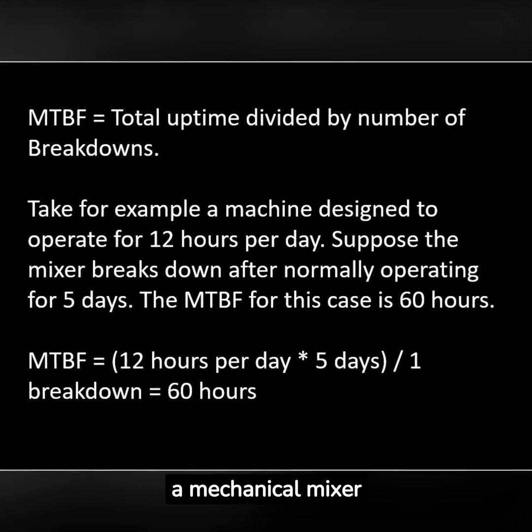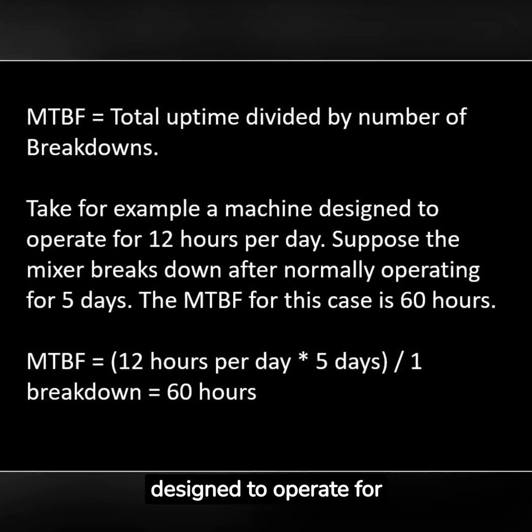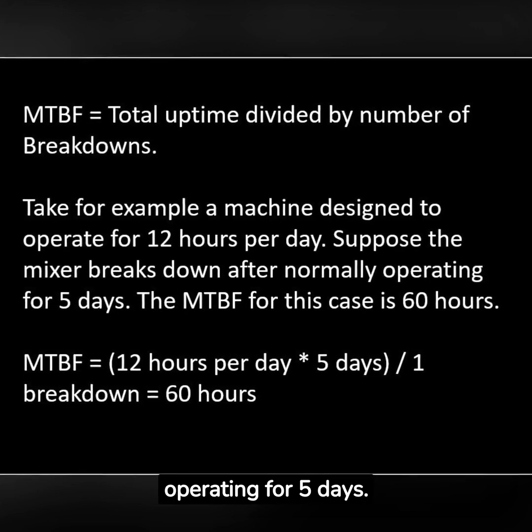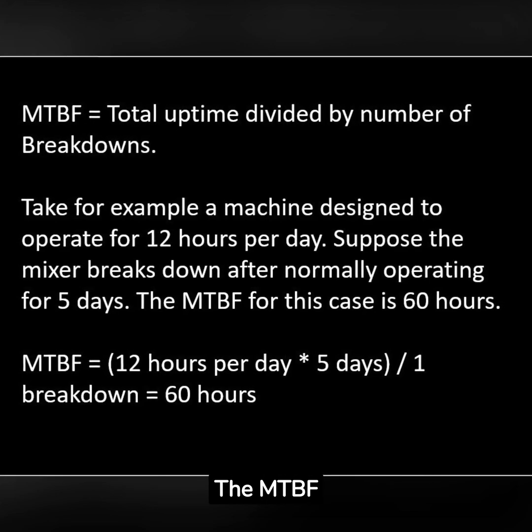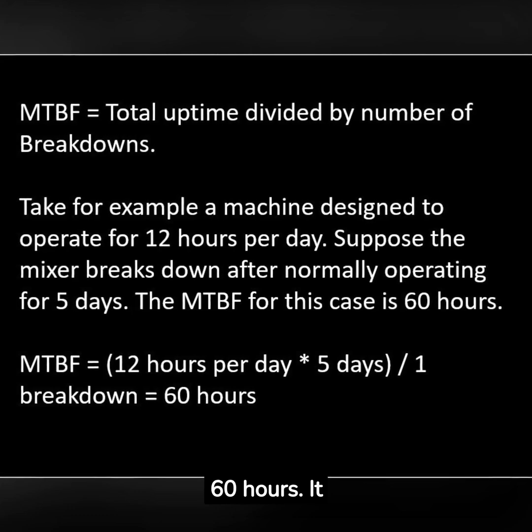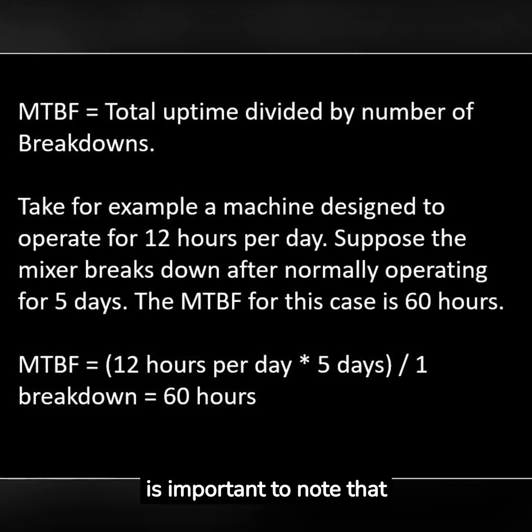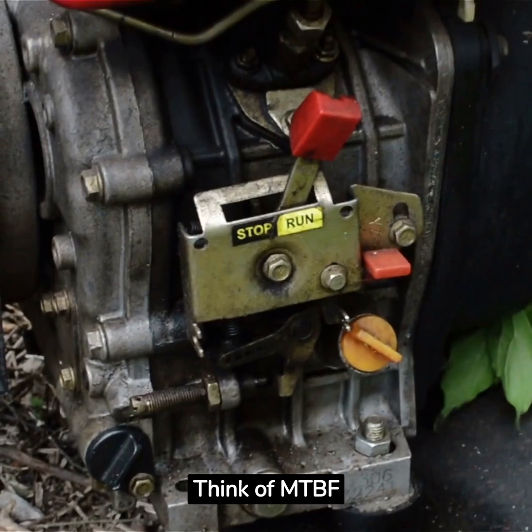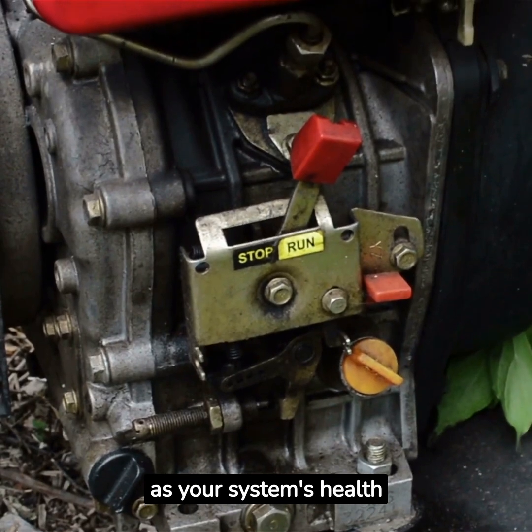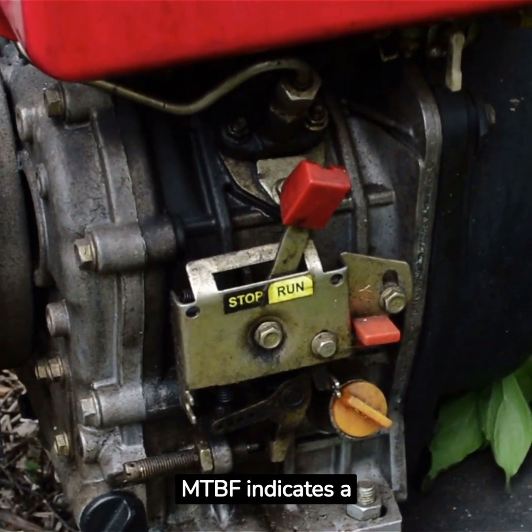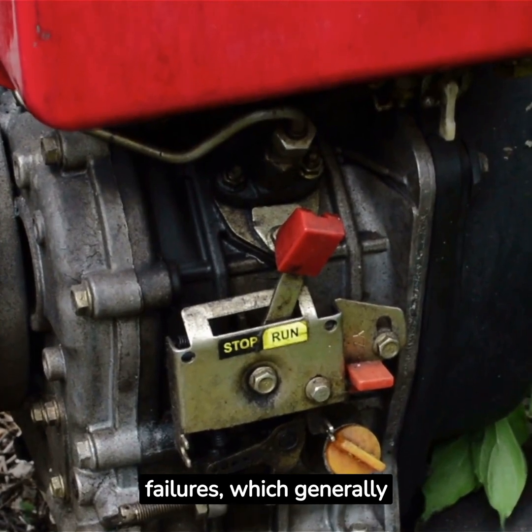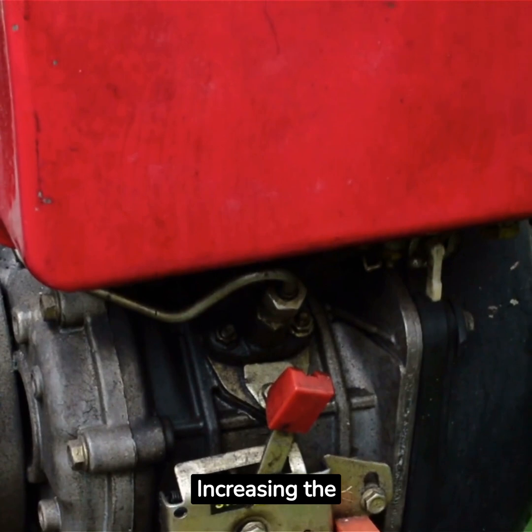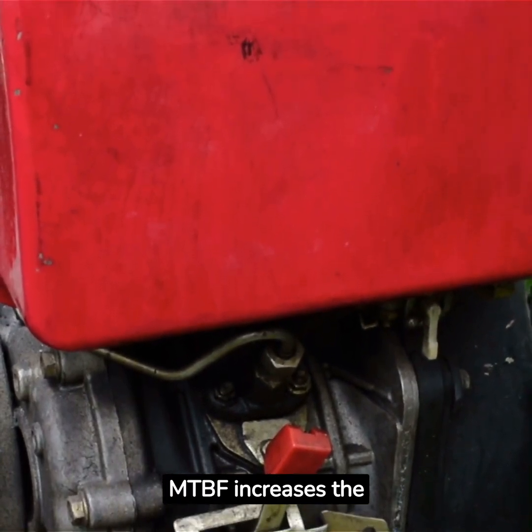MTBF is total uptime divided by number of breakdowns. Take for example a mechanical mixer designed to operate for 12 hours per day. Suppose the mixer breaks down after normally operating for 5 days — the MTBF for this case is 60 hours. It is important to note that MTBF is applicable only to reparable items. A higher MTBF indicates a longer time between failures, which generally means a more robust and reliable system.